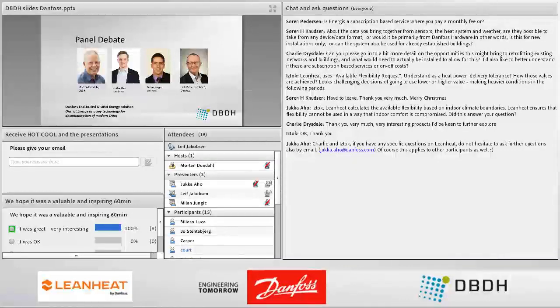So these are some of the key points and some of the key advantages. And also that we always have the hydraulic balance. We know the balance between, now we reach a point where we don't have more pump capacity. So in worst case, we'll have to increase the temperature and vice versa. So this kind of balance in the network is very important, and that we learn from our history also, take that into account for future calculations. So these are some of the major things I would like to say.